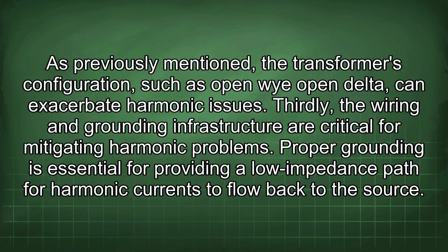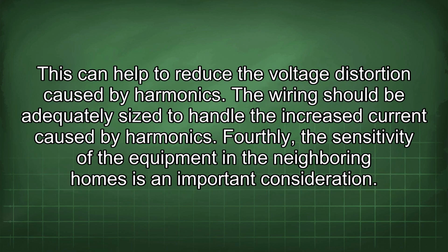Thirdly, the wiring and grounding infrastructure are critical for mitigating harmonic problems. Proper grounding is essential for providing a low impedance path for harmonic currents to flow back to the source. This can help to reduce the voltage distortion caused by harmonics. The wiring should be adequately sized to handle the increased current caused by harmonics.